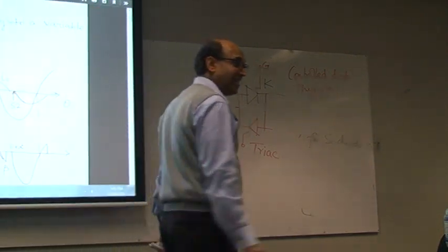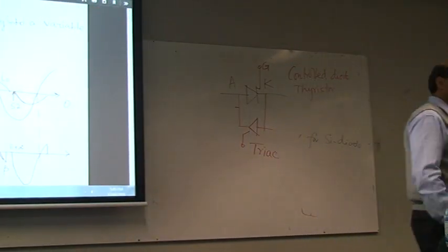Just listen to the noise. What actually happens when you run this at like 90 degrees is that you are not allowing the whole cycle, and it generates a lot of harmonics. And those harmonics produce that sound.